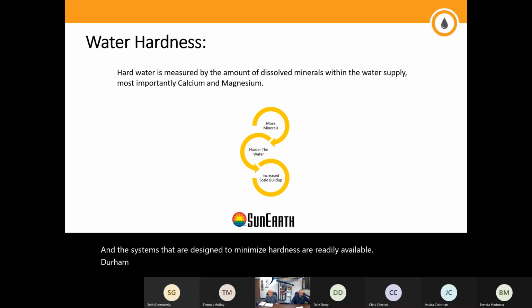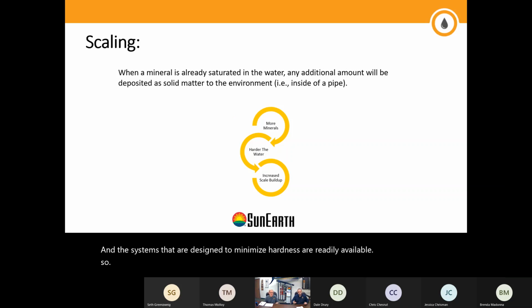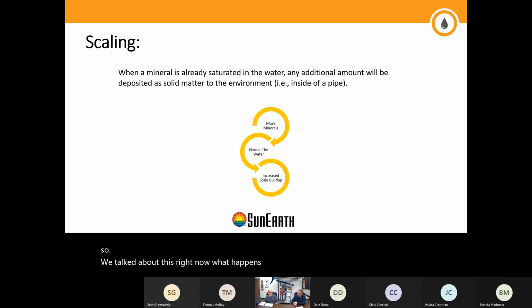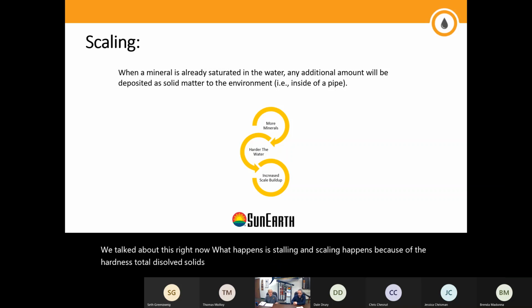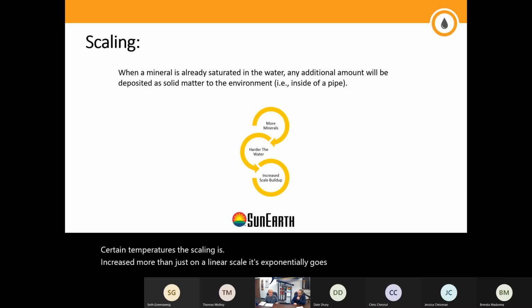So, what happens with scaling? Scaling happens because of hardness, total dissolved solids, and temperature. Since we're heating water, the temperature rises above a certain point, and scaling increases more than just on a linear scale—it's exponential. It goes up quite a bit once you get above usually 140 degrees, where scaling starts to occur.